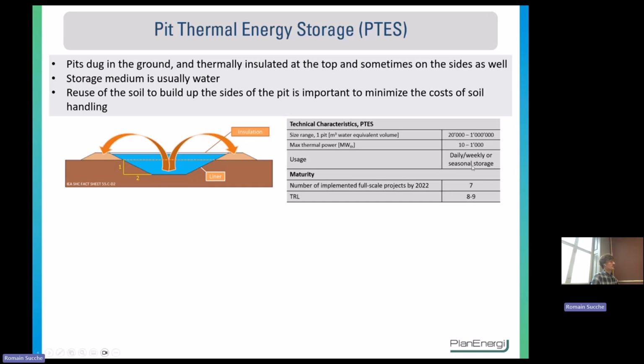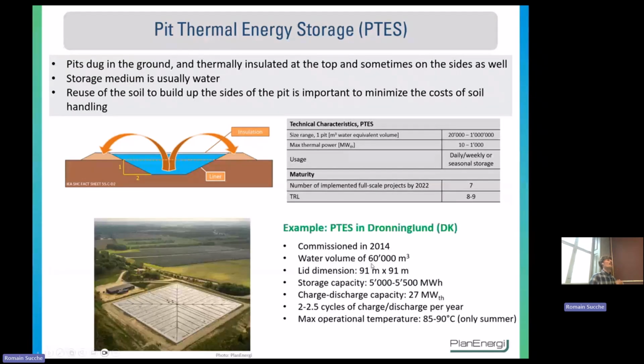And that can also be used for seasonal storage because that was how it was first implemented, basically storing solar heat from summer to winter. Also a quite mature technology, but a bit fewer implemented projects, though a bit more in 2025 and more are to come. And the example that was chosen was the one in Dronninglund in Denmark, with a water volume of 60,000 cubic meters and 2.5 charge-discharge cycles per year. And we can see here the solar panel field, and here the pit thermal energy storage.